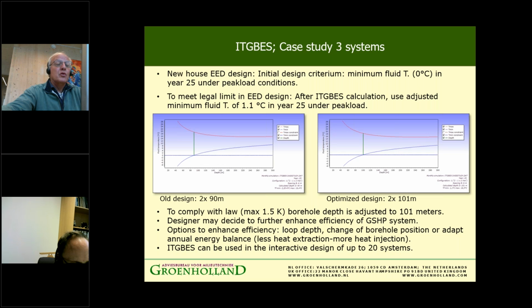So first of all, you have to deal with the legal limit if you want to stay within it. To meet the legal limit in your EED design, after doing the ITGBES calculation, you can adjust the fluid temperature by 1.1 degree in year 25. So you raise your criterion in your initial EED design. That means your minimum fluid temperature is not 0 degrees C, but 1.1 degrees C. And then you can see from the EED results that in the previous design you had loops of 2 times 90 meters. You need to improve that temperature to stay within the legal limit. It means, if you don't change the positions, you have 2 boreholes, you require 2 loops of 101 meters. So to comply with the law, to have the maximum of 1.5 degree Kelvin interference, you have to adjust your boreholes to 101 meters.